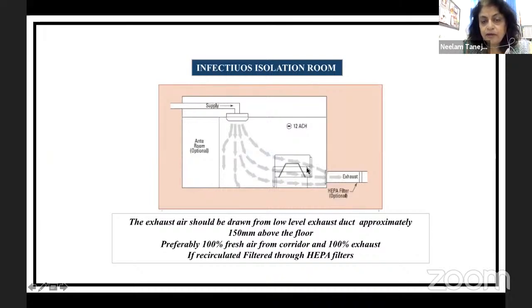supply is coming. This is the bed of the patient, and it is being exhausted at the floor level. The exhaust duct should be approximately 150 millimeter above the floor. Preferably, we give 100% fresh air from the corridor and exhaust 100% of the air. And preferably we use a HEPA filter at the exhaust. If the air is getting recirculated, then you need a HEPA filter both at the entry and the exit.